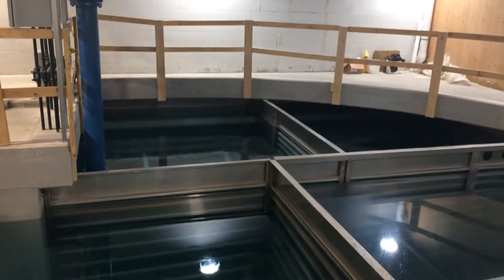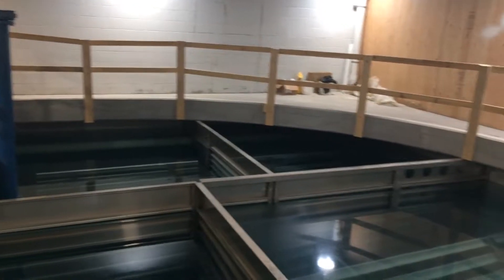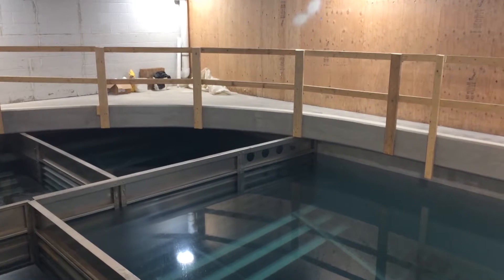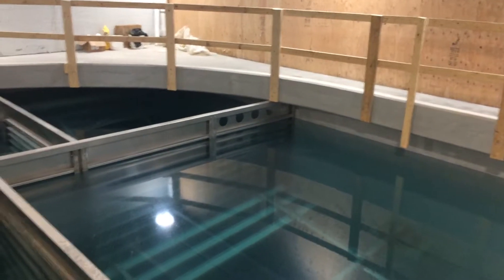This is a four-stage horizontal paddle wheel flocculator system. It's compartmented into stages with the stainless steel MegaWall. You can see here, the MegaWall has ports or openings sized accordingly to Ten States Standards for velocity. It serpentines through the system, travels into a small collection chamber, and then into the quiescent zone within the basin.